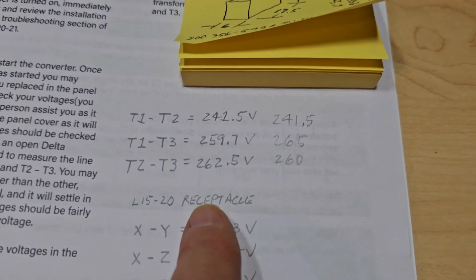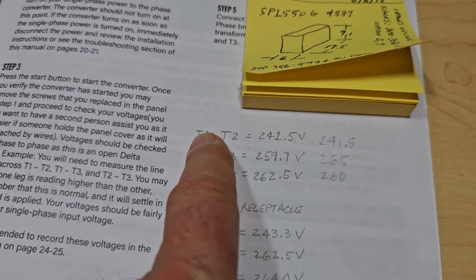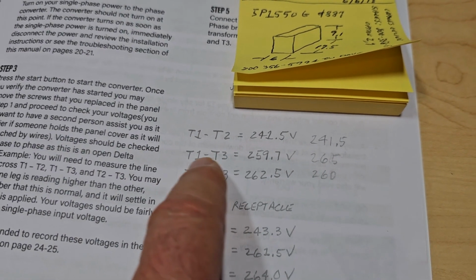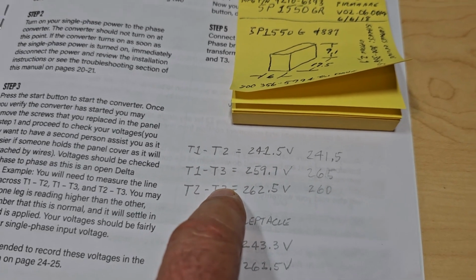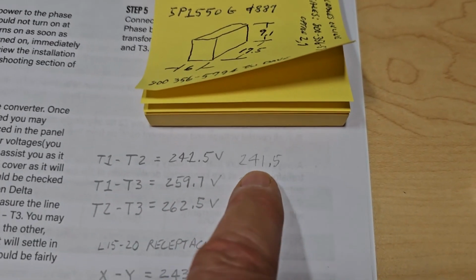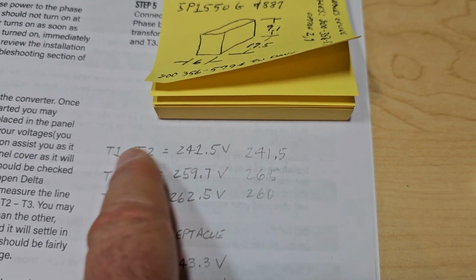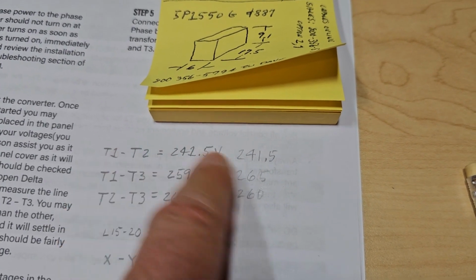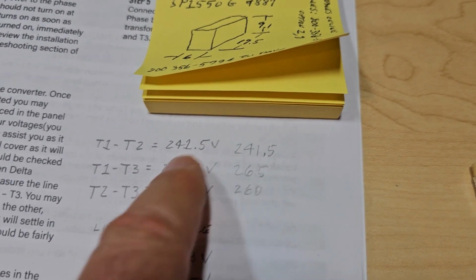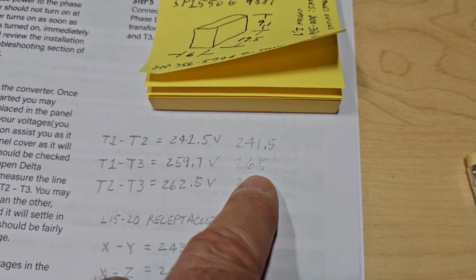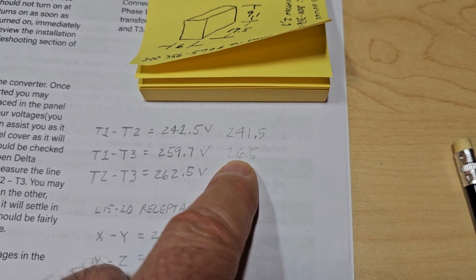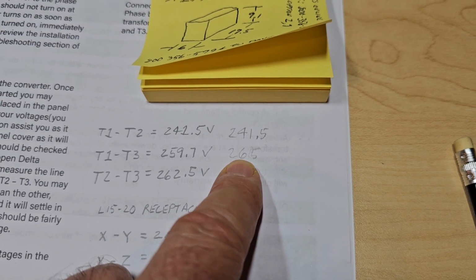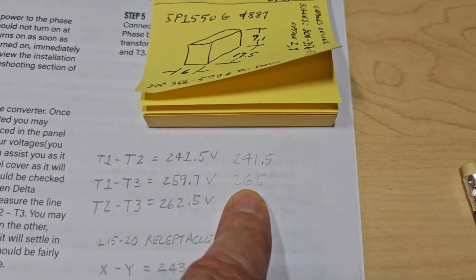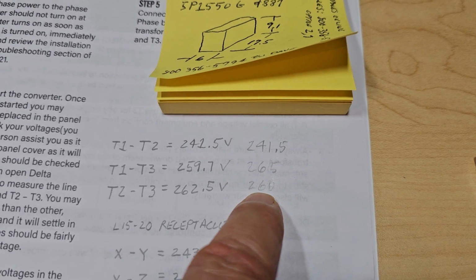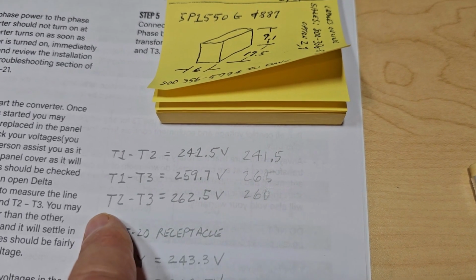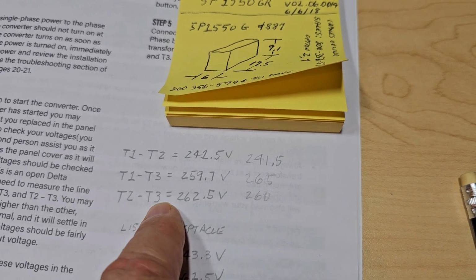Okay, so at the back of the phase converter, inside there from terminal T1, which is the top, T2, which is the middle, and T3, which is at the bottom, I get 241.5 volts. Comes straight through from the main. So that's good. But when I get down to the manufactured line, I get 265, which is not good. It can't be that high. And I get 260 between the middle terminal, T2, and the lower terminal, T3.